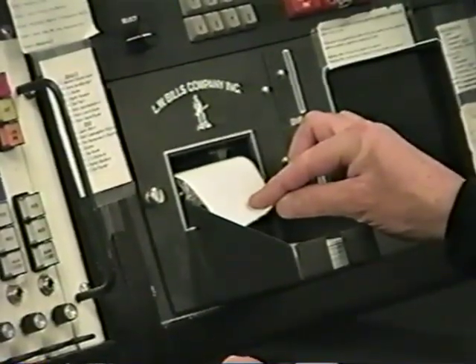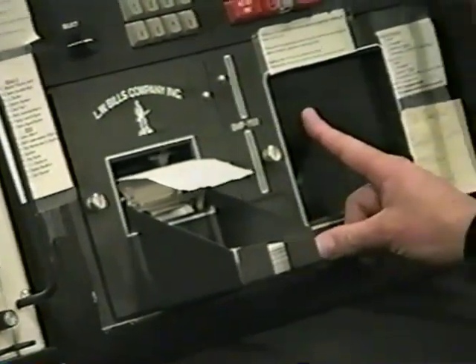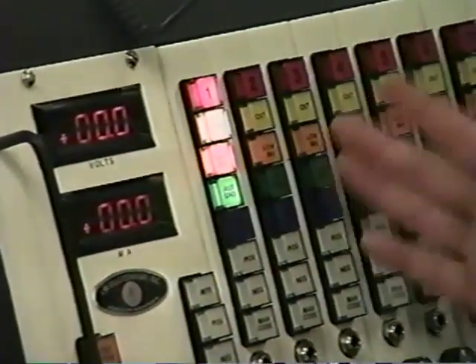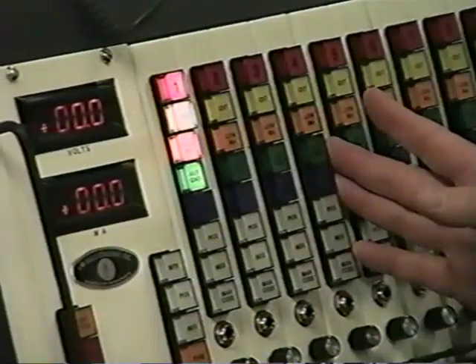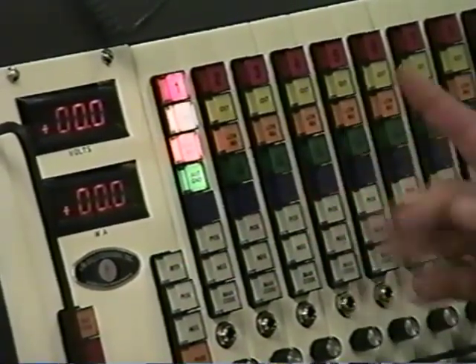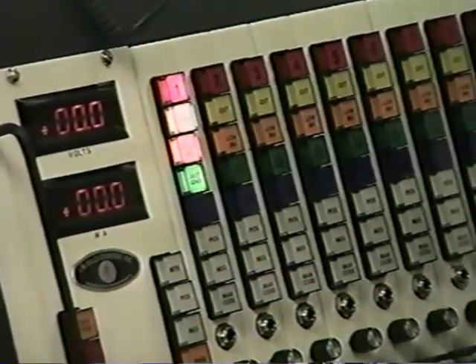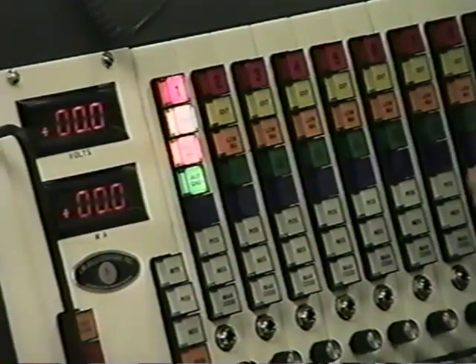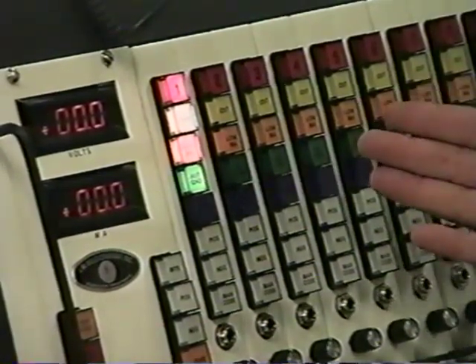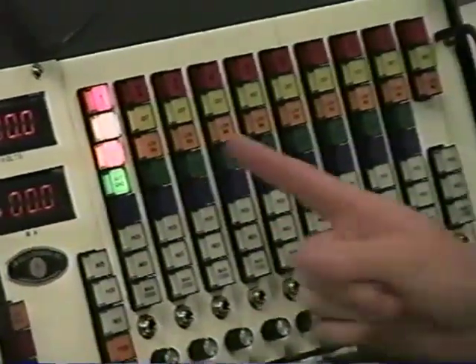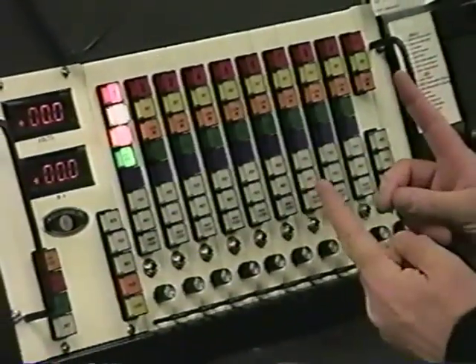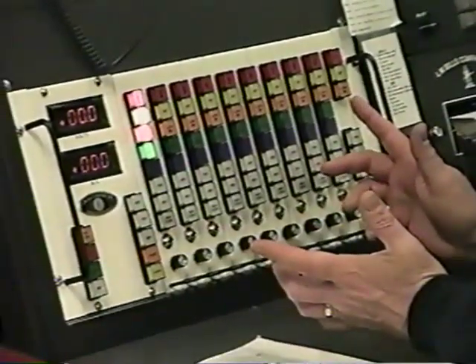The printer just printed to let us know circuit one. We received what's called one stray blow on circuit one. You can see that over here it says open one. What has happened here is there's a feature built into this machine where the circuit has gone into automatic ground. If a wire is to break on the circuit, it doesn't matter. All of a sudden, each side becomes its own separate circuit and works through earth ground. And after however long that took, about 20, 25 seconds, it went into automatic ground. So the system will still work even though one side of the wire is broken.